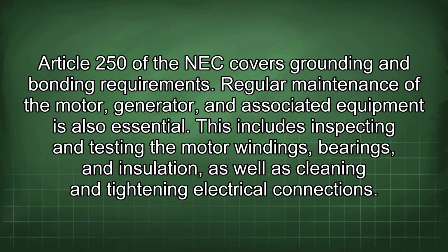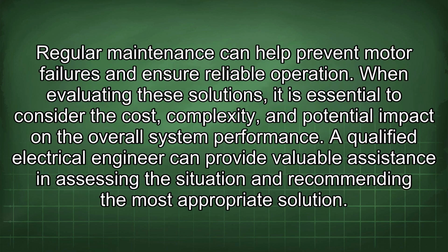Regular maintenance of the motor, generator, and associated equipment is also essential. This includes inspecting and testing the motor windings, bearings, and insulation, as well as cleaning and tightening electrical connections. Regular maintenance can help prevent motor failures and ensure reliable operation.